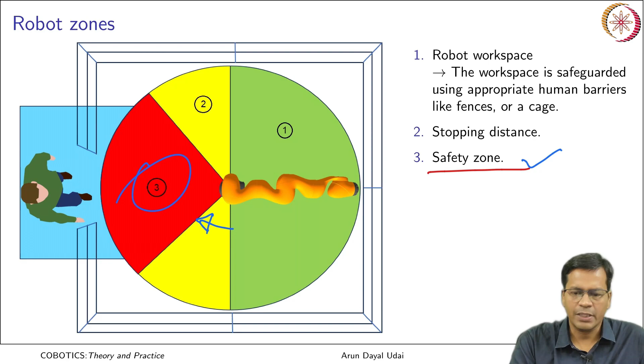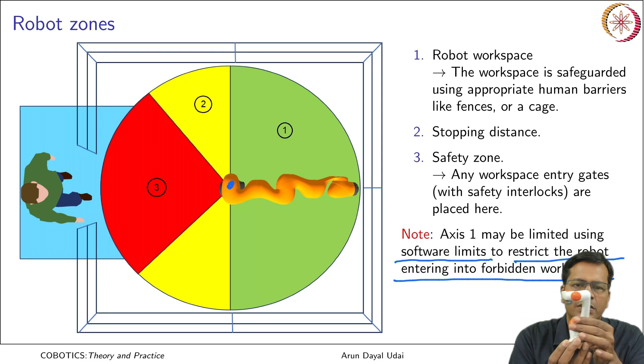Any workspace entry gates with the safety interlocks are placed here. So normally the gates are placed here. Axis 1 may be limited using software limits to restrict the robot from entering into the forbidden workspaces. Axis 1 is the first axis of the robot, that is the vertical axis. If you check this robot, it looks like this. So this is axis 1. That is the first axis that may be limited. In this case, that would cause the robot not to even enter somewhere over here. So you can always limit this angle.